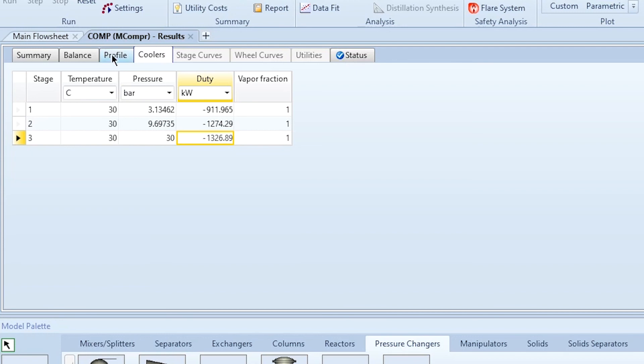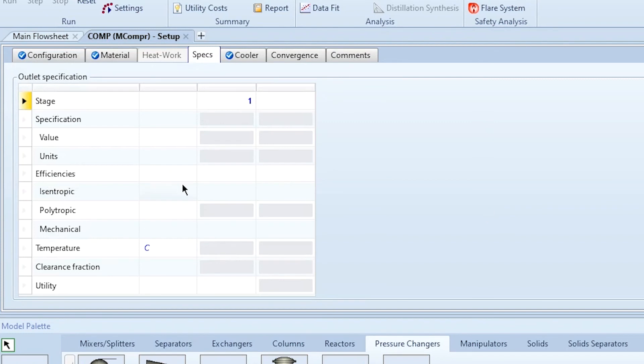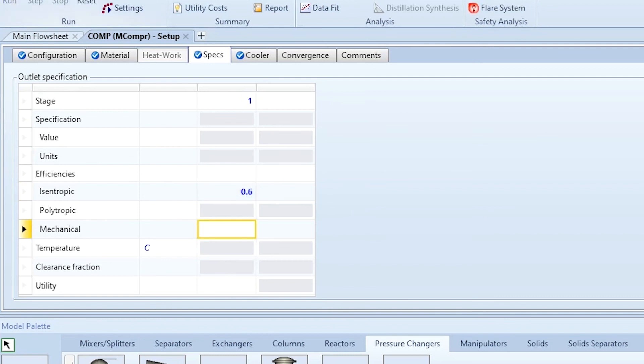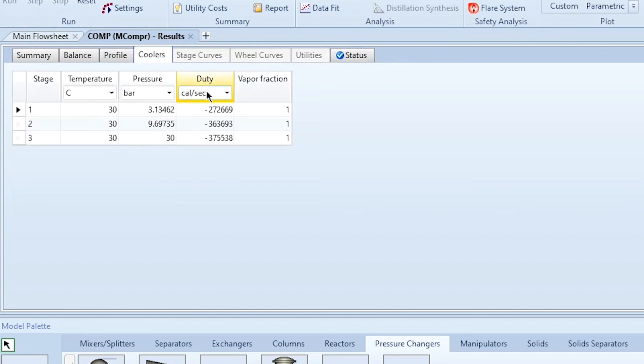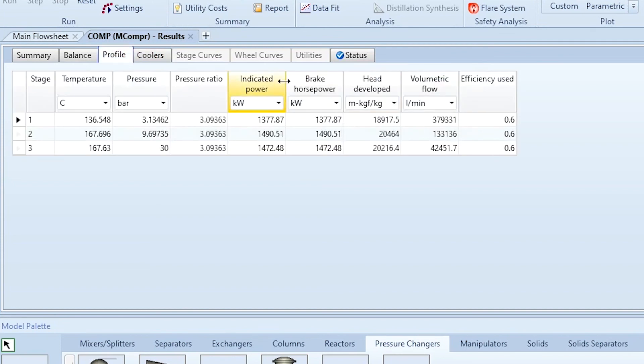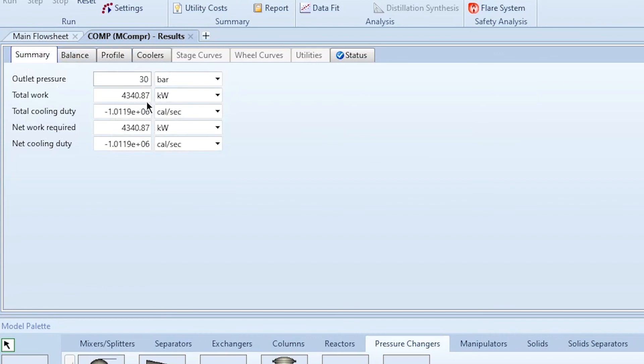If you want to set a specific compression efficiency, for example 0.6, enter it in the Specs tab and click Run. Going back to results, the cooler duties change — earlier it was around 900 kW, now it is 1141 kW. In the Profile, the efficiency is shown as 0.6 and the results are updated accordingly, showing a significant difference due to the lower efficiency.